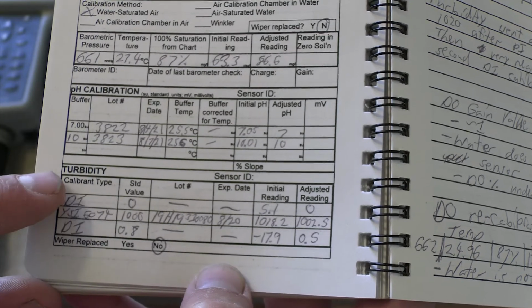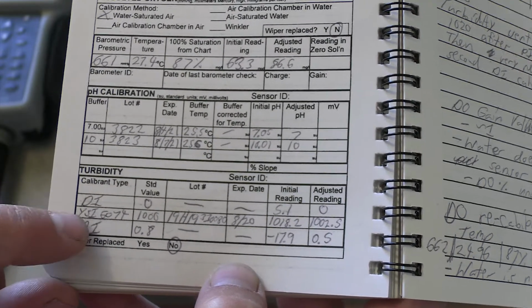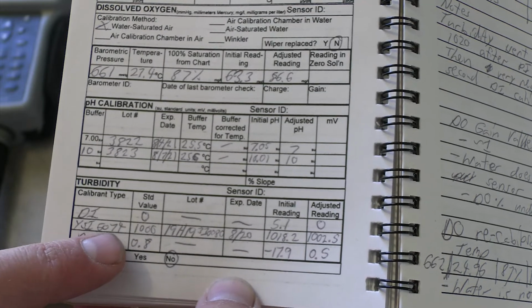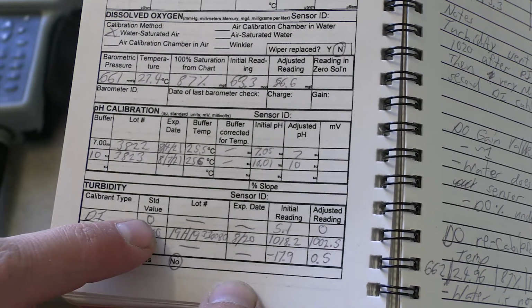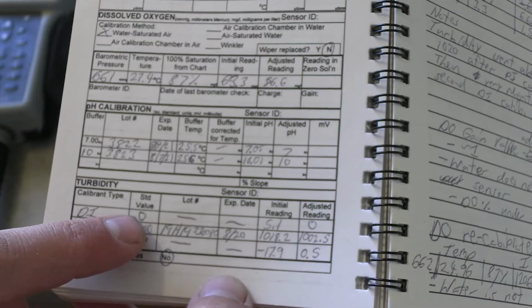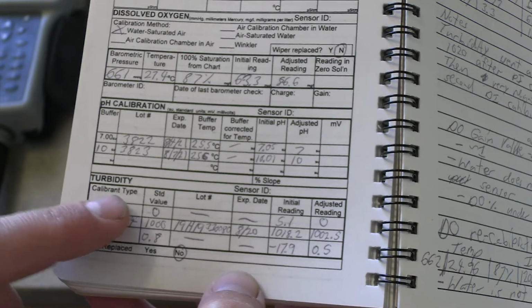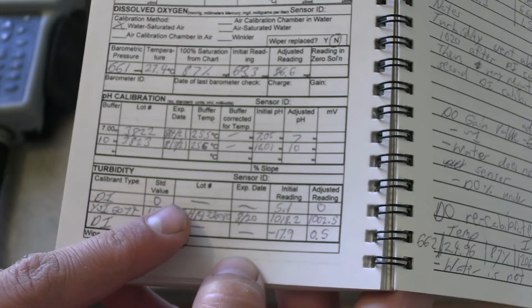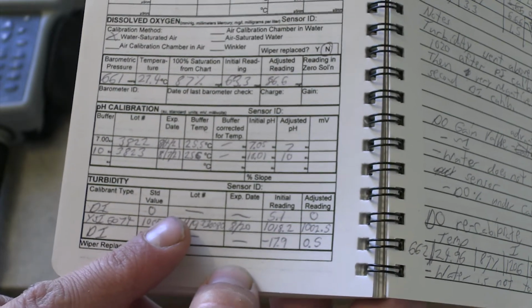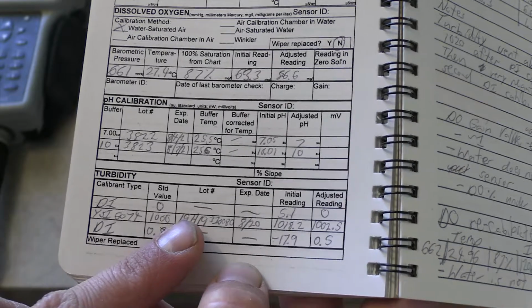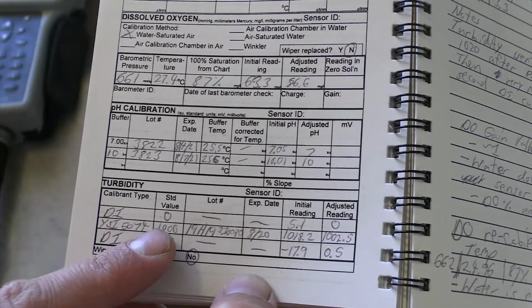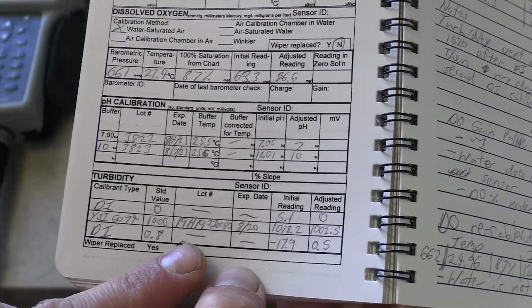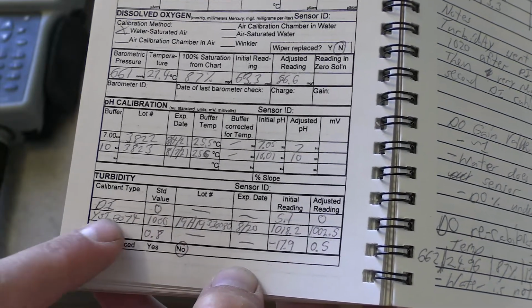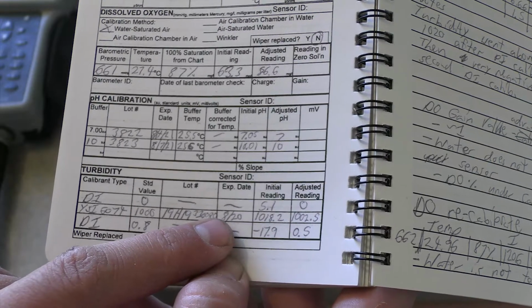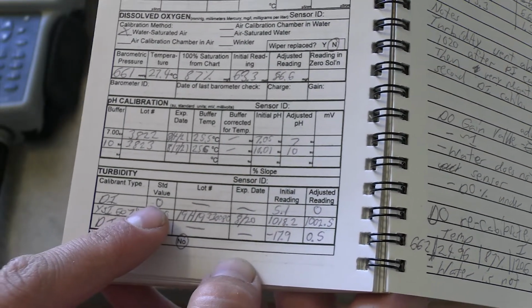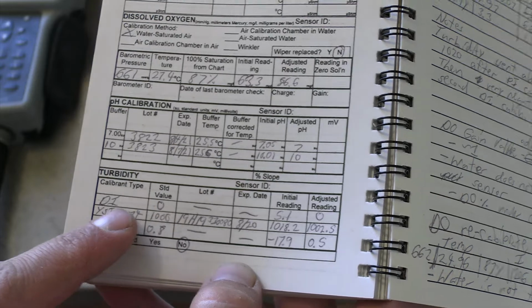So there's just a total of 4. And turbidity is also done with 2 solutions. It's done with DI water and this YSI 6074. So DI water just has a standard value of 0. You need to make sure it's deionized water, because otherwise it can have particles in it. Sometimes I guess you could use reverse osmosis water, but it's better to use DI because it's completely pure. So just make sure you put the standard value and the lot number in for the YSI solution, and then the expiration date for the YSI solution, because as far as I know, I don't think there's an expiration date for DI water.